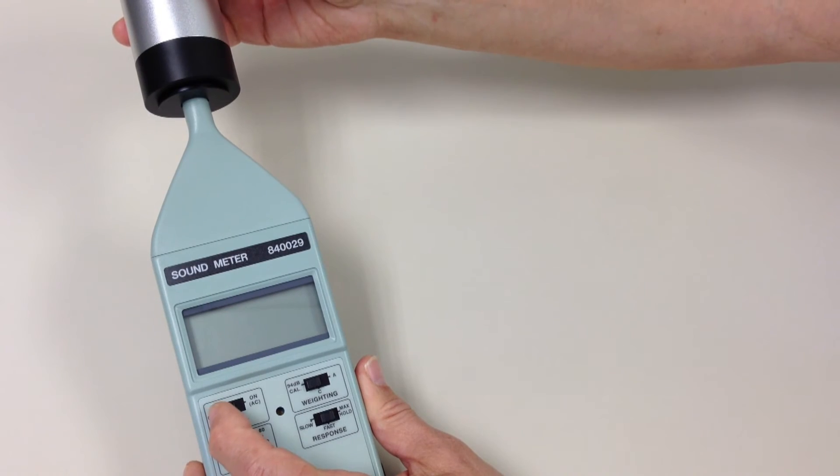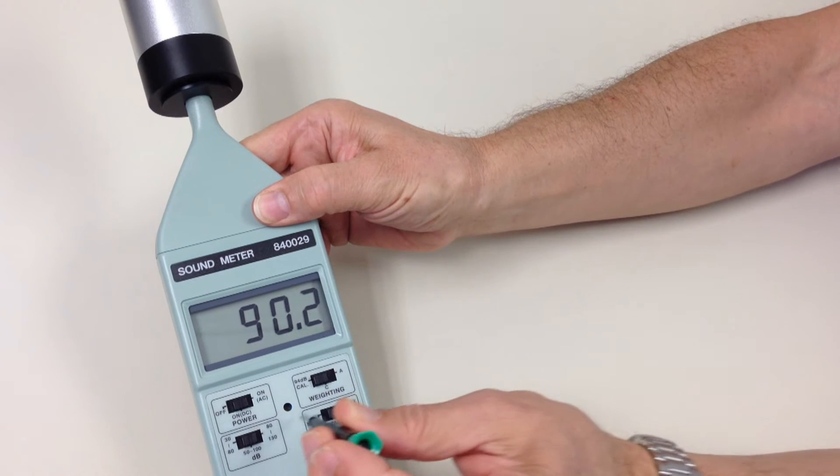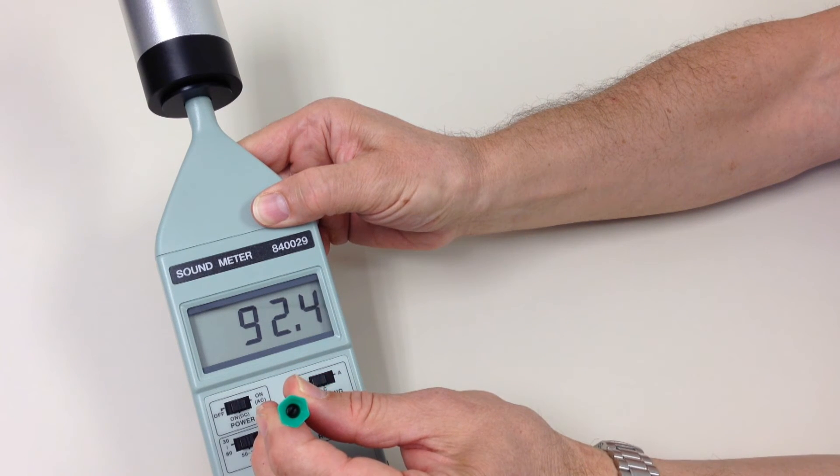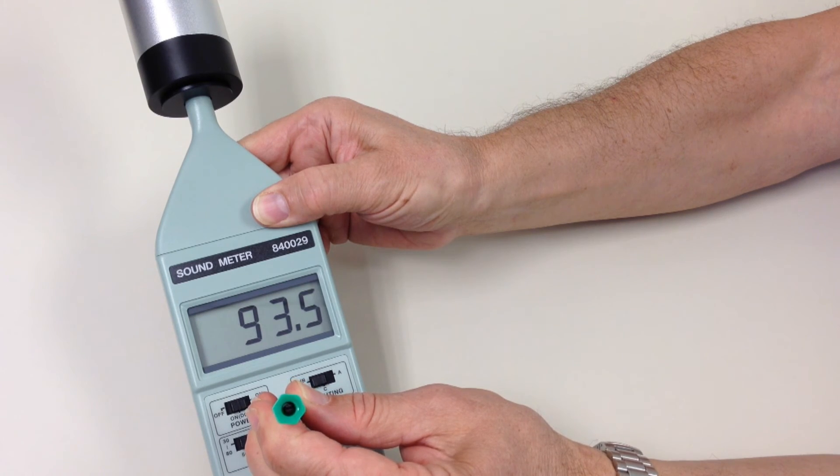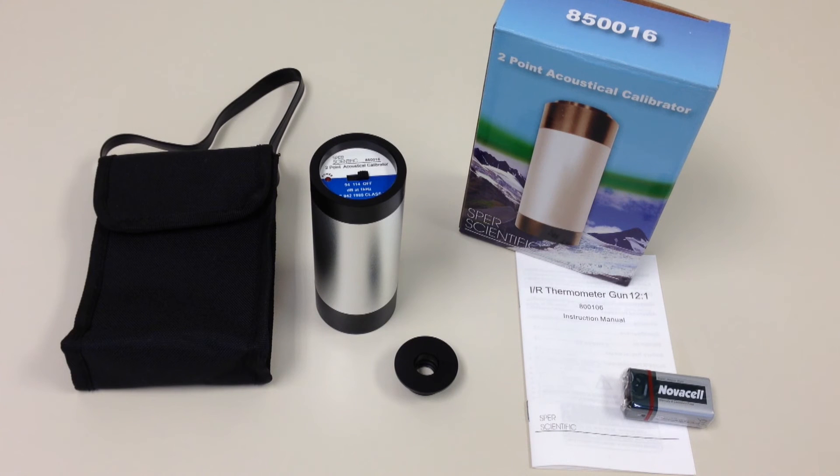Turn your sound meter on. And now adjust your potentiometer until the sound meter reads to the calibration point, in this case, 94 decibel.